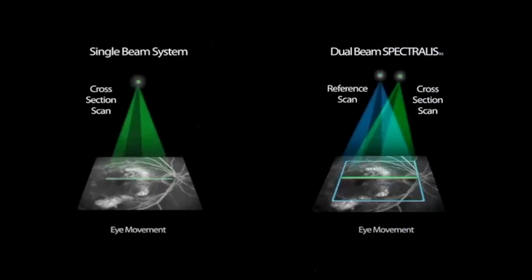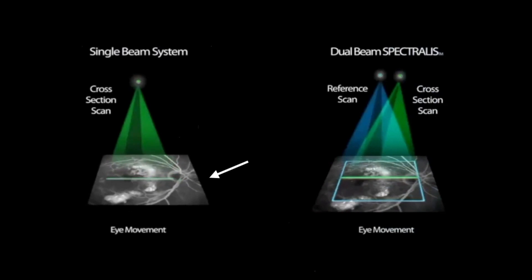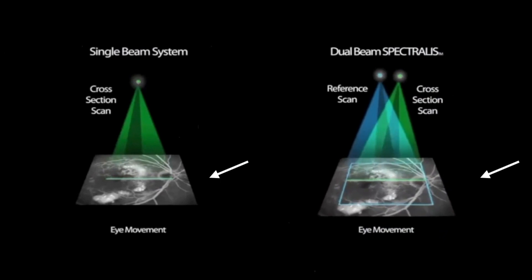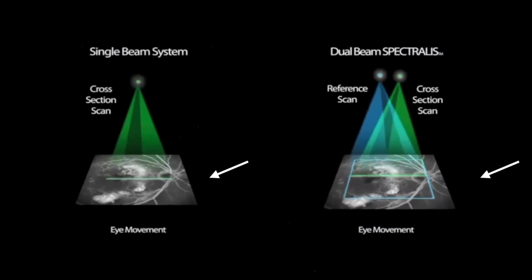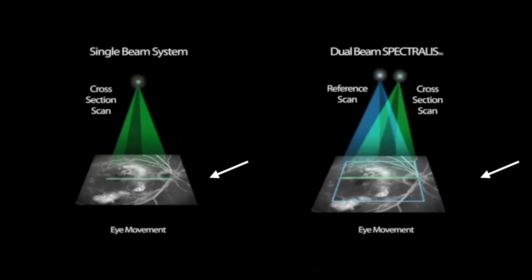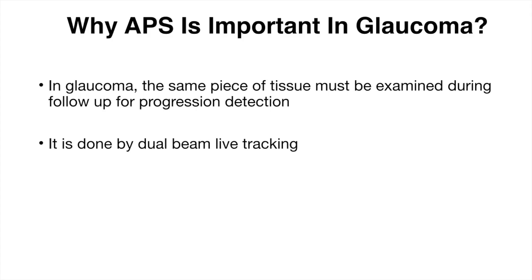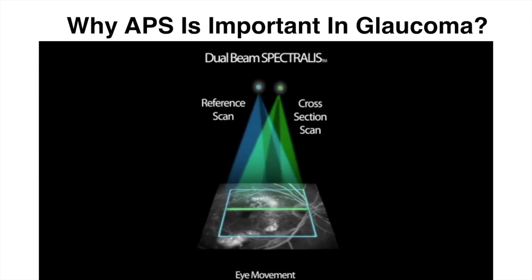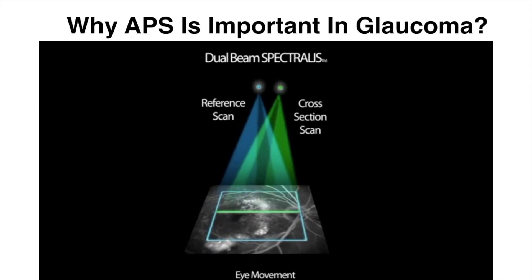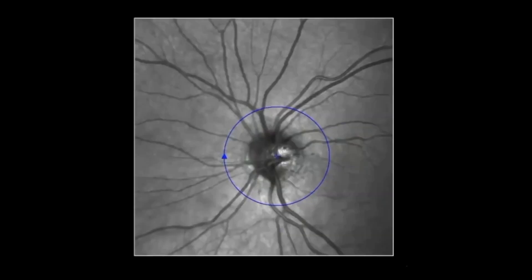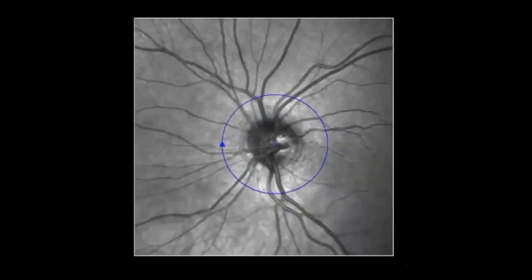A video comparison shows the single beam system on the left: the scan does not compensate for eye movement. On the right, the dual beam Spectralis compensates for eye movements with the help of a reference scan. With Spectralis dual beam live tracking, the same piece of tissue is examined during glaucoma follow-up. The anatomic positioning system can detect glaucomatous progression at the level of 1–2 microns difference between two visits.